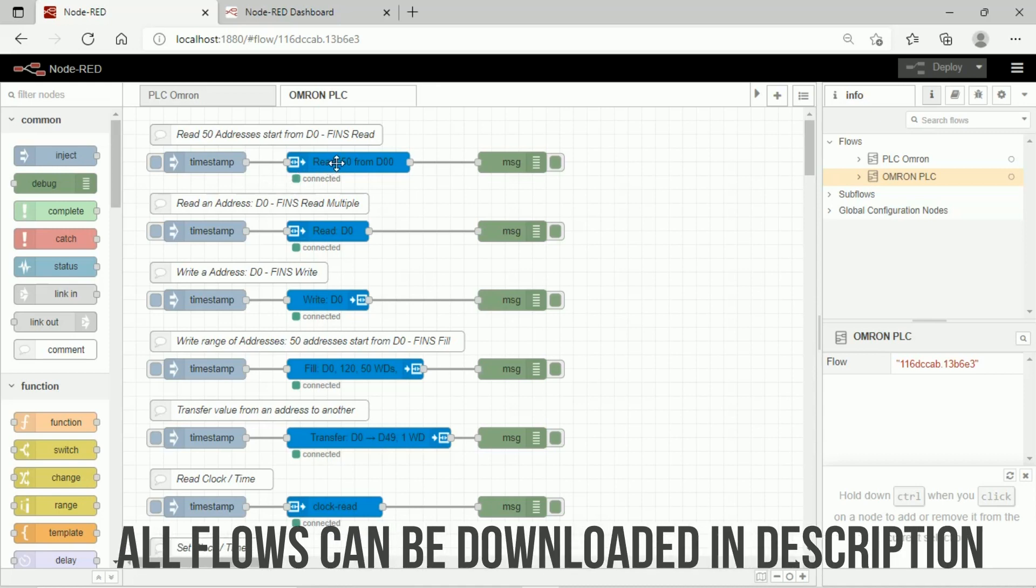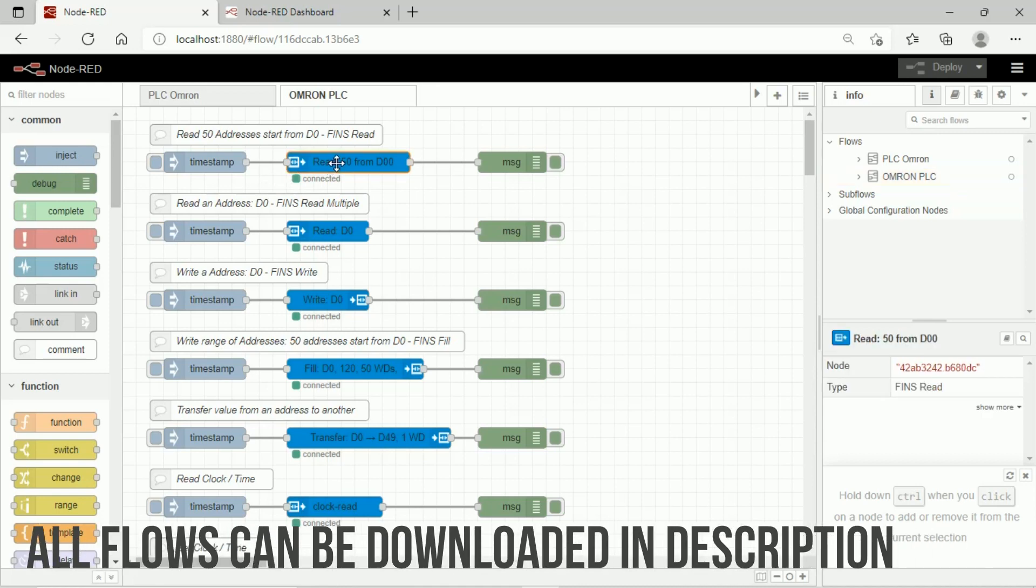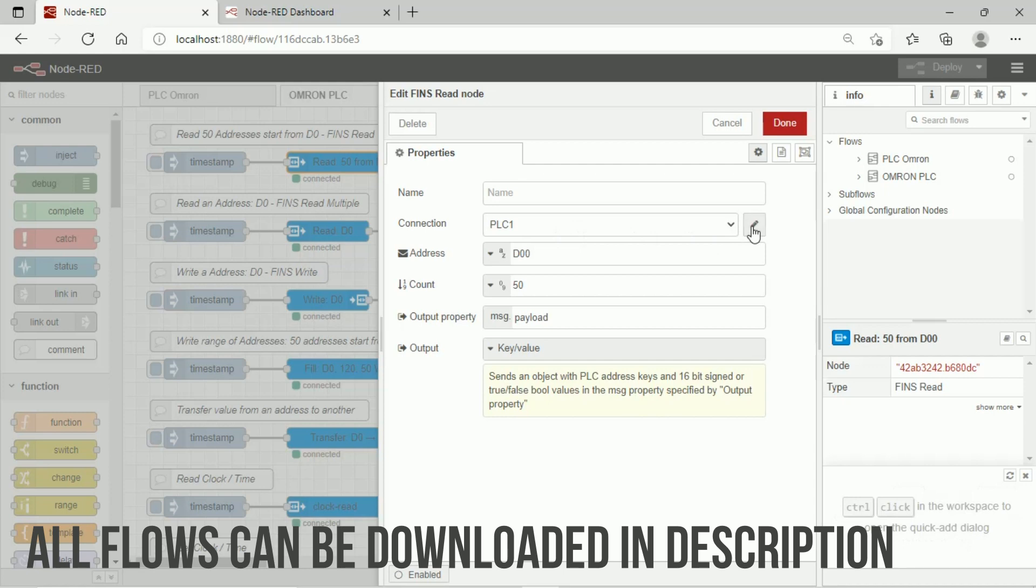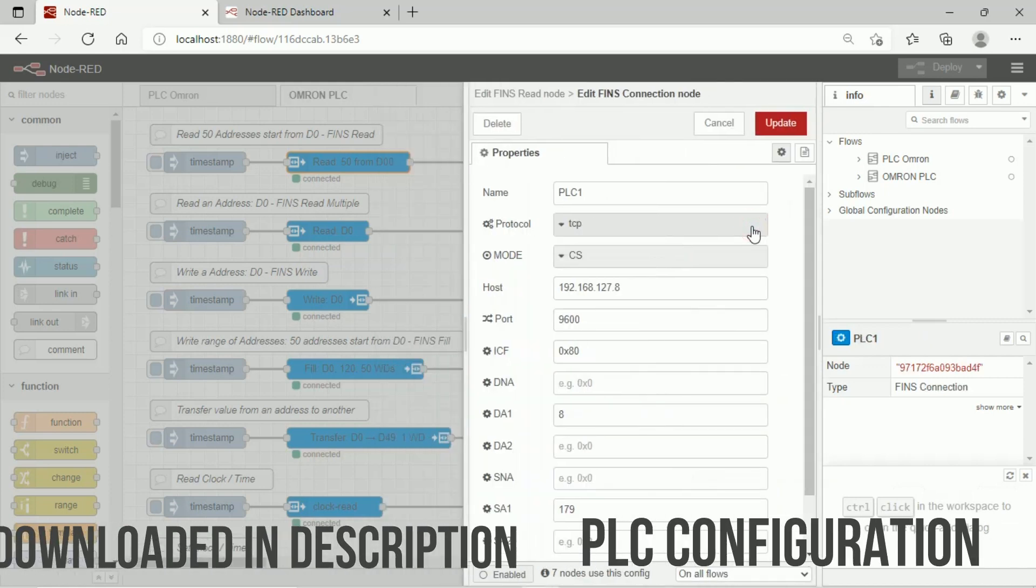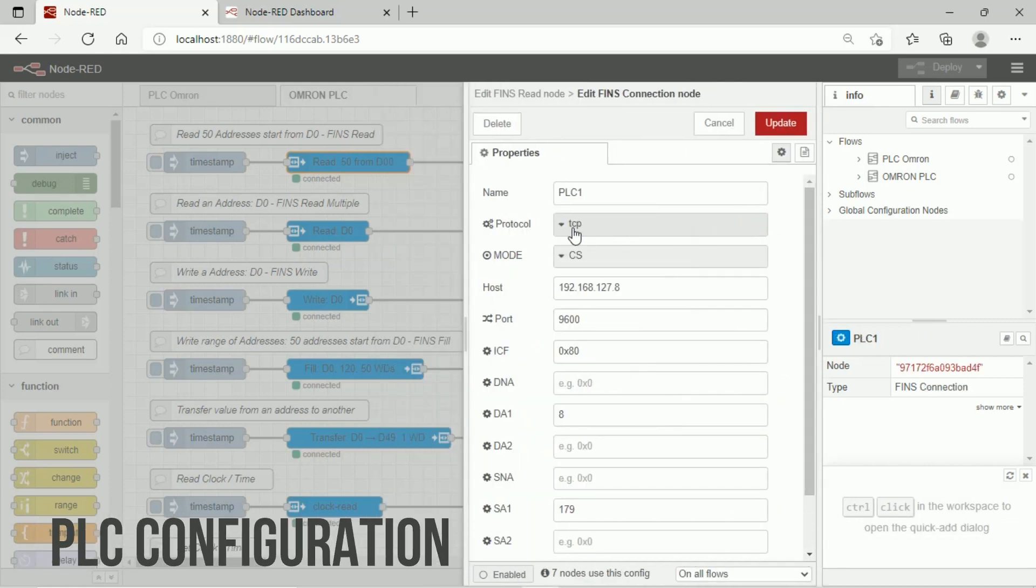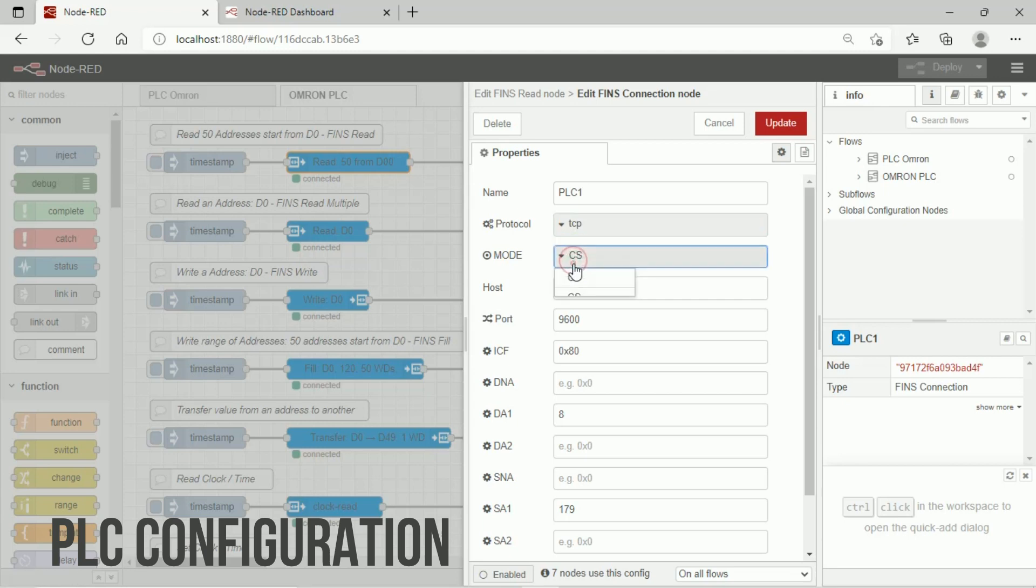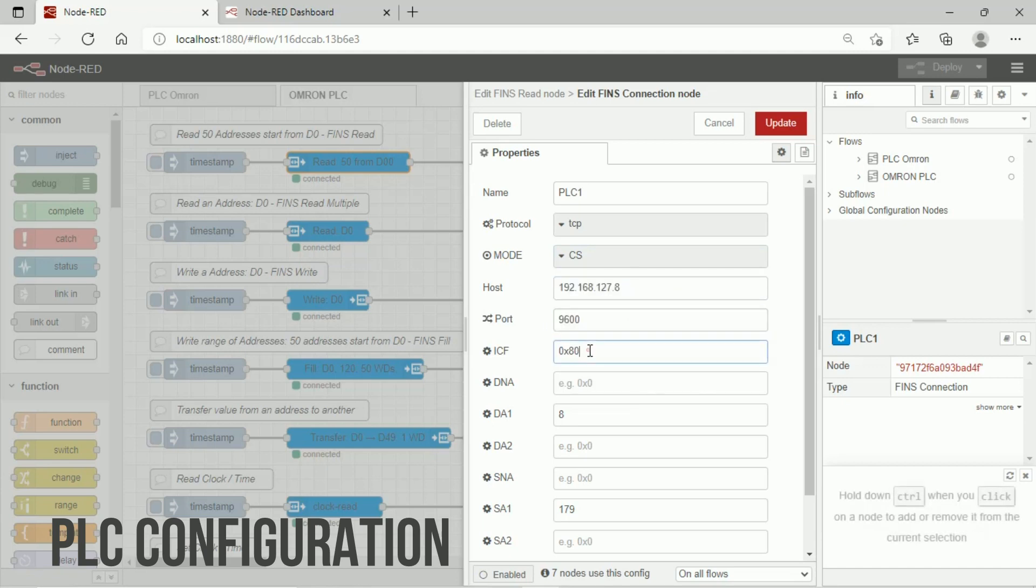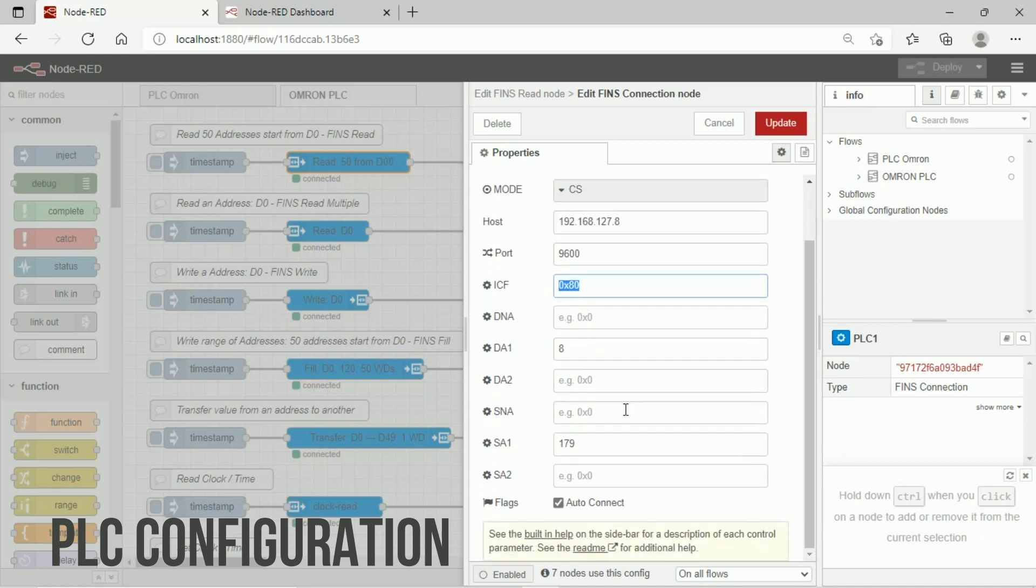Select an Omron node, then select the PLC name, and click Edit icon to start to configure PLC. Set protocol to TCP, choose in mode based on your Omron PLC's model. In this video, I use CS model. Fill host same with PLC's IP address, follow all settings same with this tutorial. DA1 is same with node number and IP address.